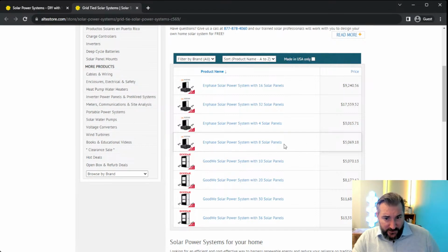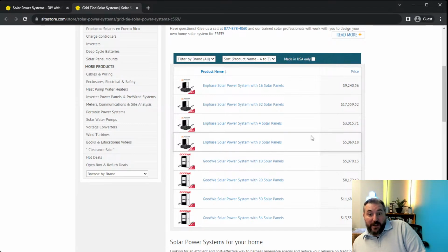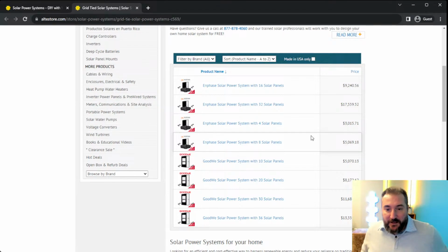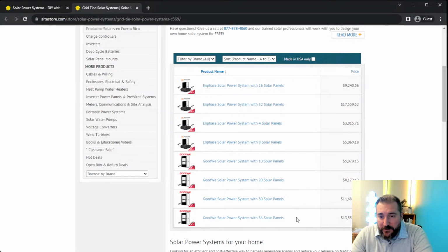The shade tolerance is certainly going to be better with the micro inverters if you're dealing with partial shade, or different orientations and directions. For instance, I have a system that's east-west, half the array facing east and half facing west, and in that situation having microinverters is beneficial because I don't have to worry about the different orientations having different outputs across strings. That's why some people prefer to go with micros. But if you have a nice big open orientation without a lot of shade issues or different directions, you can save a lot of money with a string inverter.